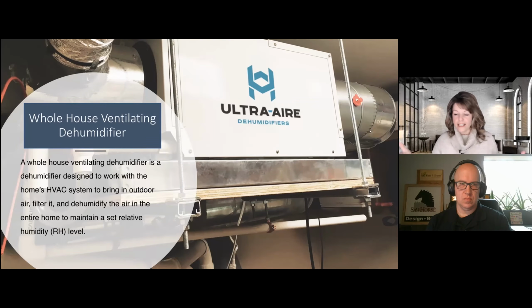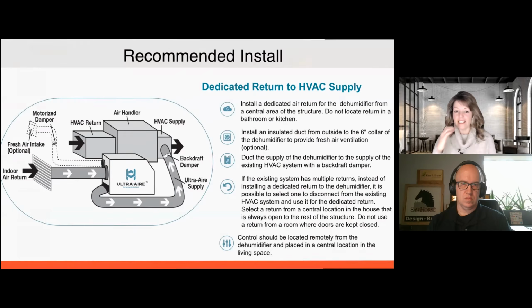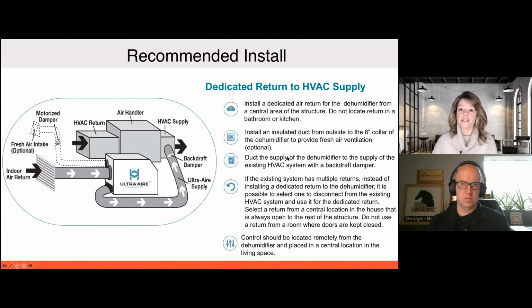So it is a dehumidifier that is going to integrate with the HVAC system in order to dehumidify the entire home. You can actually bring in that outdoor air and filter it. But again, this dehumidifier is going to focus on getting to a set RH. And how it is integrated, this is our recommended install. And so what we like to do for energy efficiency purposes, this install would have a dedicated return to the dehumidifier. And then we would tie into the supply of the HVAC system.